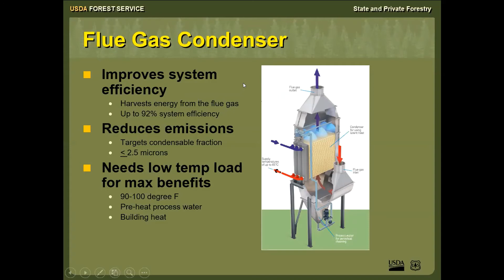It targets the condensable fraction of the pollution stream in the flue gas, and those are the items that normally end up condensing into small particles, predominantly below 2.5 microns, once they exit the stack. The one thing that Dan mentioned is that we need a low temperature load to get the maximum benefit from this flue gas condensation system. And if you have a demand or can utilize that 100-degree hot water, either for preheating process water or for building heat with low temperature emitting systems, you can gain some significant advantages in your system efficiency. And I want to talk a little bit about where we see some of those advantages.